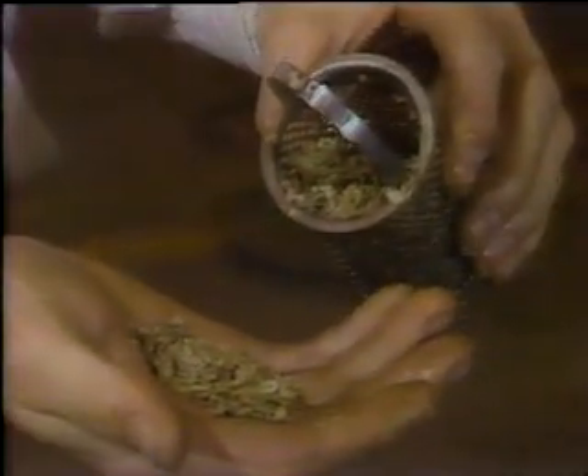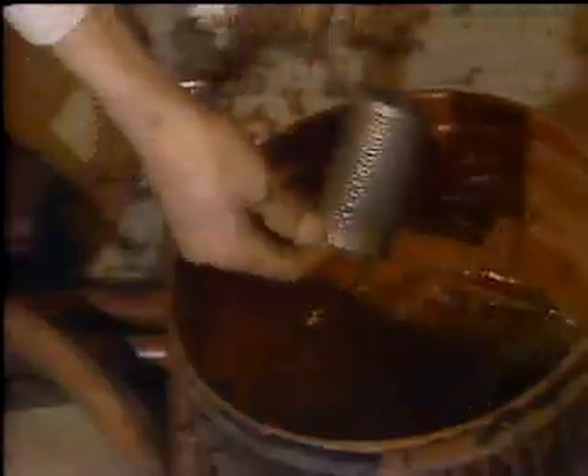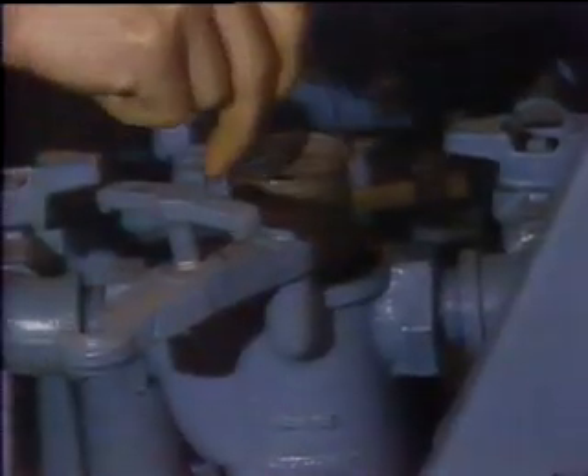Look at that. That's a lot of scale in that basket. It was restricting the blowdown flow through the heat exchanger, which was limiting the exchange of heat to the feed water. That causes colder water to be entering the system and can create the problem you were having. You should clean it before you even try to start the unit up, and while the unit's operating every 8 hours by bypassing the strainer.